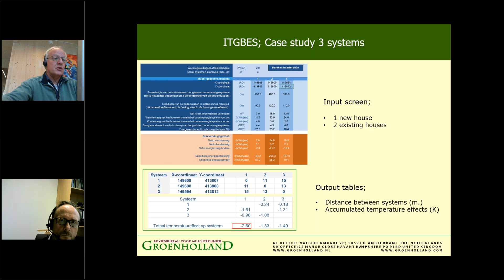If you use, for instance, EED as your design tool, your initial design criterion, you may have used, for instance, a criterion of a minimum fluid temperature in year 25. Let's say if year 25 is long enough for your calculations, you could say what I set as a threshold in my design is 0 degrees temperature as a minimum under peak load conditions in year 25. So in the coldest month of the year, in year 25, you run your heat pump for a number of hours, which you define as a peak load condition, and then you say, I do not want my temperature to drop below 0 degrees C. What you found here, of course, is that there is a negative temperature effect of 2.6 degrees on this system.